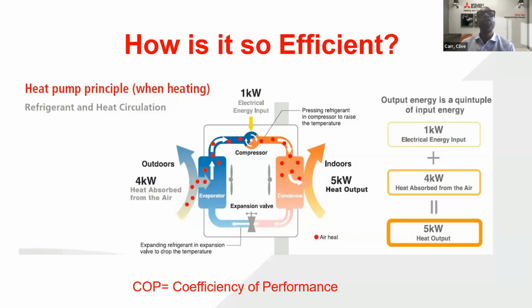Again, this is just another illustration that better explains the efficiency of the heat pump, where you could see 1 kilowatt of energy, for example, is being used. So you're using 1 kilowatt of energy from the grid. But with that 1 kilowatt that you're using to operate the heat pump system, it's absorbing 4 kilowatts of heat from outside. So that additional 4 kilowatts of heat absorbed from outside, plus the kilowatt of heat that you're generating from the compressor, gives you 5 kilowatts of heat that's being dissipated inside.